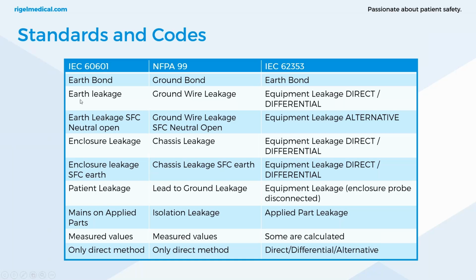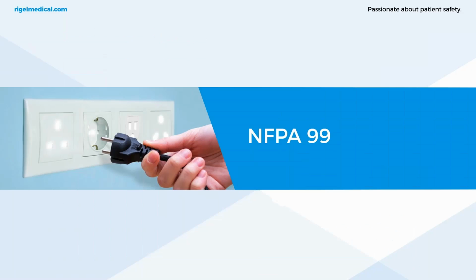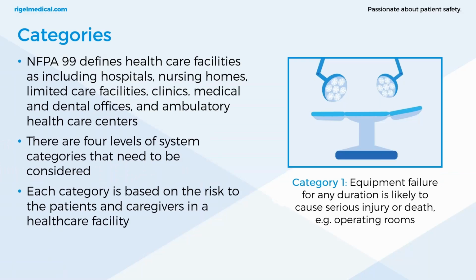This is for medical device manufacturers, where they might be doing more stringent testing. NFPA 99 has been simplified to make things a little bit easier for the end user, because quite frankly, we haven't really got time to be performing the level of testing that comes from IEC 60601. So NFPA 99. Firstly, I'll talk a little bit about the categories, and it does apply to electrical safety.